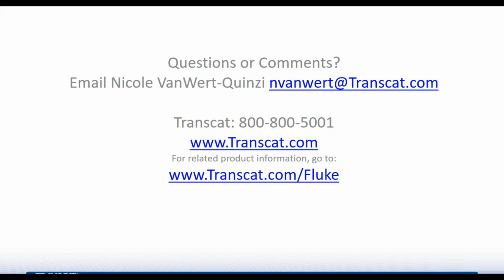How many test results can be saved on a documenting calibrator? Oh, it's a good question. Conservatively, you can put at least 50 on there. I've had cases where it's gone a lot higher, but I would recommend that you always clear out the calibrator after every shift. So, if you've got a tech doing, let's say, between 5 and 10 calibrations, I'd recommend, go out, do your calibrations, bring them back, upload those test results, and then so there's no confusion on what's been done before, after, go ahead and delete those results for the next shift. That's probably the best way I would recommend doing it.